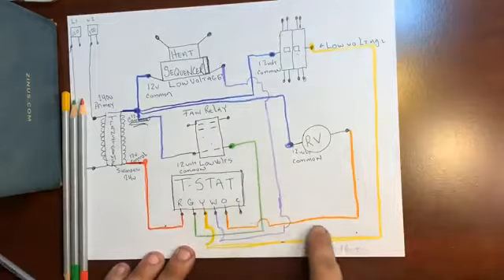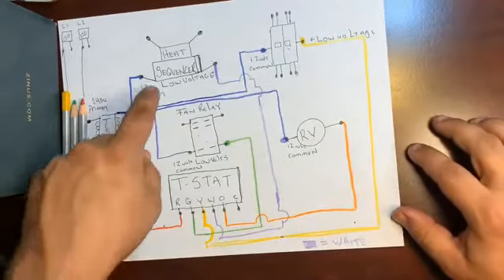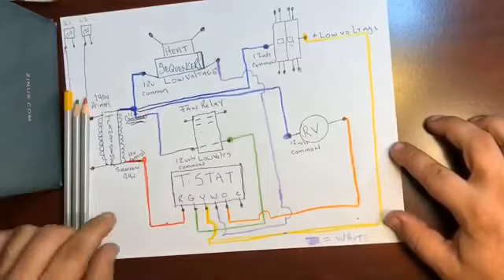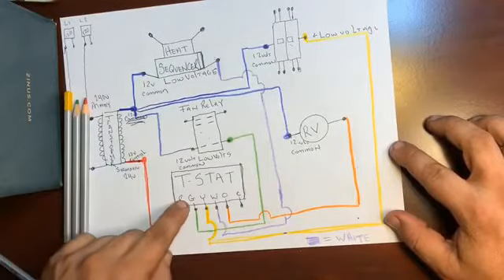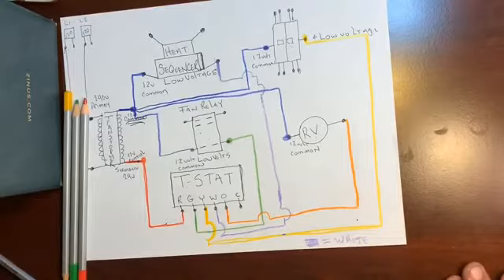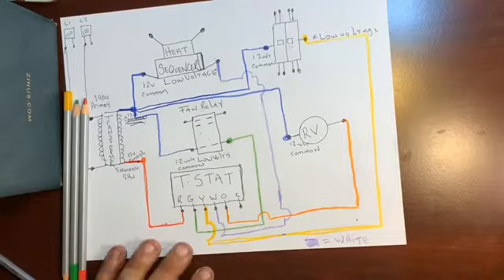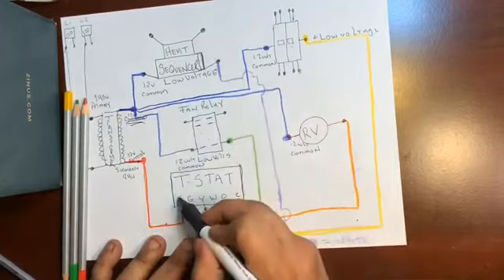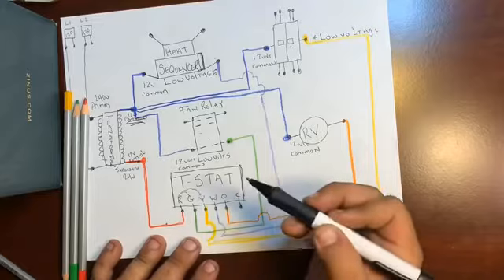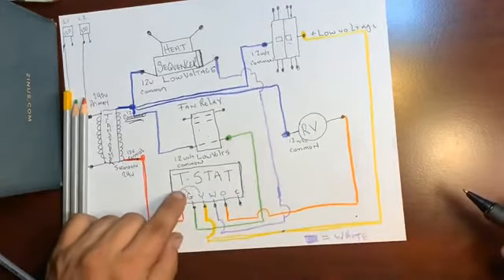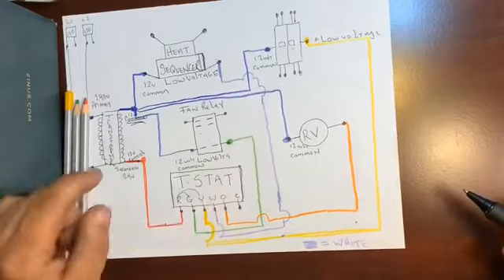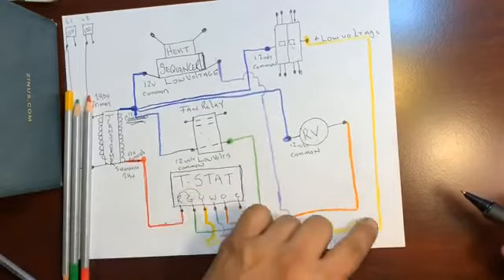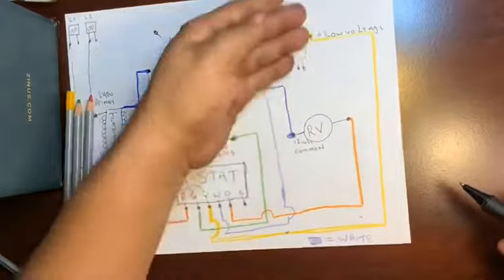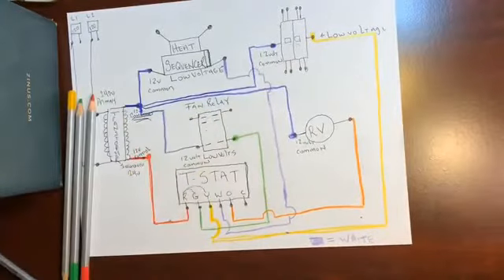Next thing, bring over the control, which are the color wires, the thermostat wires. So 12 volt at every relay uninterrupted. 12 volt control is going into the thermostat. So now what happens is when the thermostat says, hey, we need air conditioning, the red will send 12 volts to the green because that's the indoor fan motor, and it'll send 12 volts into yellow because that's gonna send, that 12 volts is gonna go through the green, turn on Mr. Fan. It's gonna go through the yellow and turn on Mr. Contactor. So now the condensing unit's on, the indoor fan motor's on, now we're cooling.